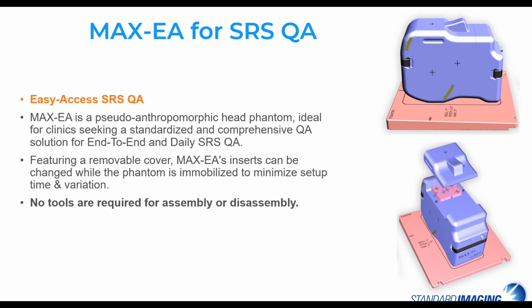Max EA is the pseudo-anthropomorphic head Phantom, which is ideal for clinics seeking a standardized and comprehensive QA solution for their end-to-end, also for SRS commissioning. The main feature again is the removable cover, which allows for the inserts to be changed while the Phantom is immobilized. And also there are no tools required for assembly or disassembly of the Phantom.